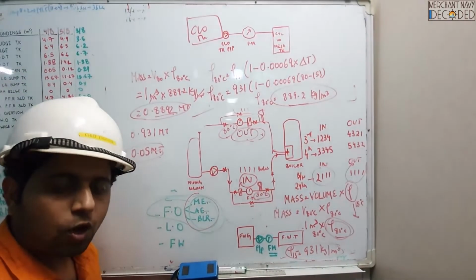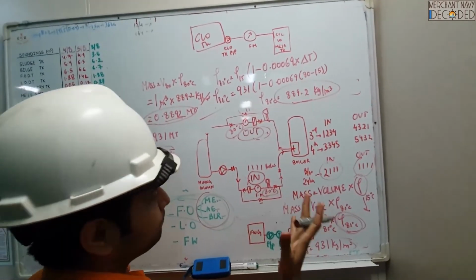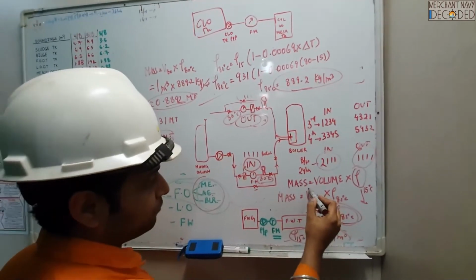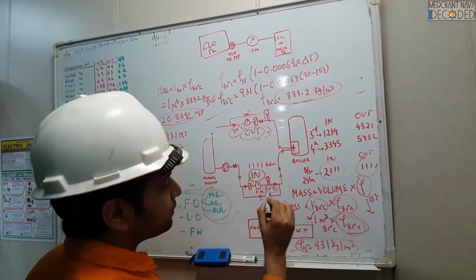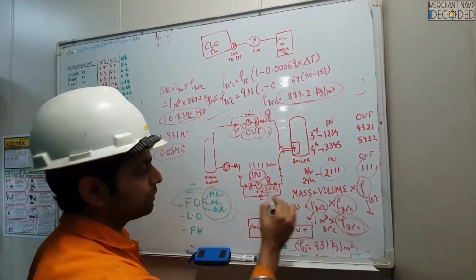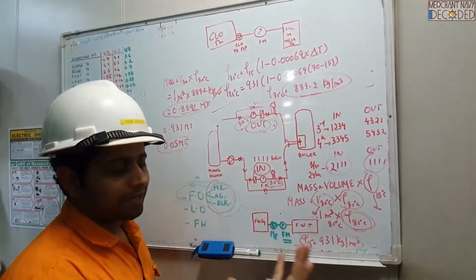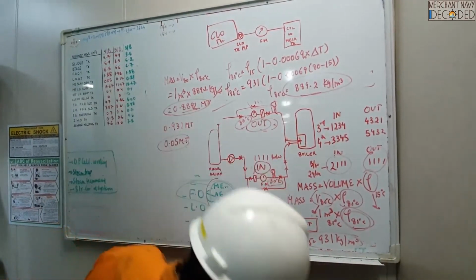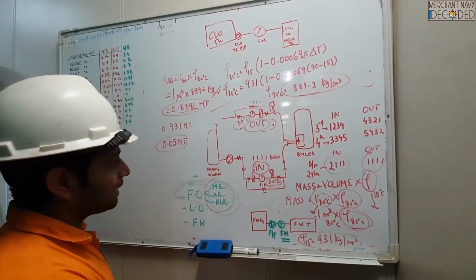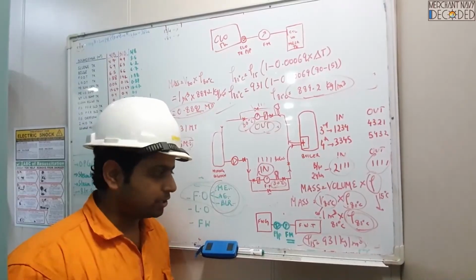So please always ensure that when you are calculating the flow meter metric tons mass, if you have taken the volume of the flow meter, then density also has to be taken at the flow meter temperature over here, the fuel temperature at the flow meter. Copied, guys? Very, very important. Otherwise, you will have excess fuel with you, and that will be a big problem. Now, I have explained this. Now, let me take you through a small run and show you all these things.